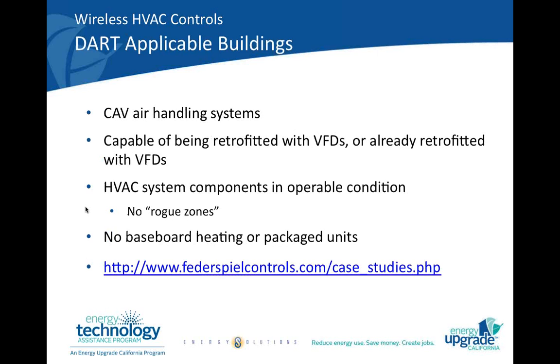So what makes a building a good opportunity for DART? Any buildings with a constant air volume system, constant air volume air handling units, are a good opportunity. They have to be, as mentioned before, capable of being retrofitted with VFDs or already have VFDs. Your HVAC system needs to be in good condition. You need to be able to operate the outside air dampers.